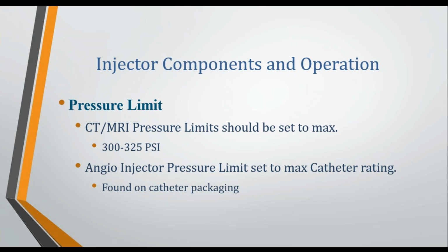General rule of thumb, though, for all CT and MRI injectors, maximum pressure limit is 300 psi. Angio, again, because CT and MRI injectors only go up to flow rates of 10 milliliters per second, because CT and MRI procedures are just slower procedures than angiographic procedures are. So slower procedures means we don't need as fast injection, so lower flow rates, lower pressures. Angio injectors, on the other hand, are capable of very high flow rates, 40 to 50 milliliters per second, so they're capable of very high pressure limits.